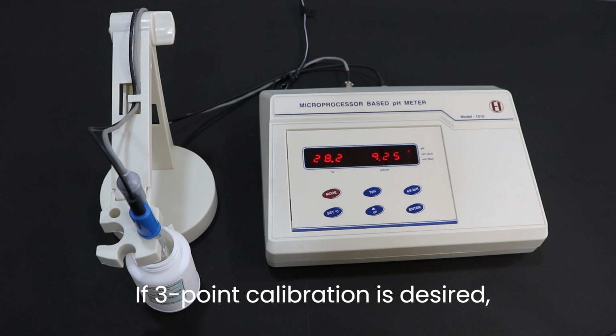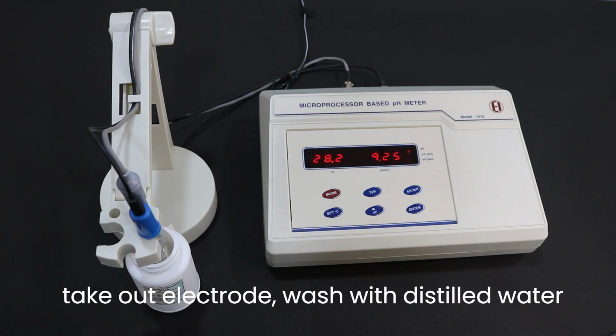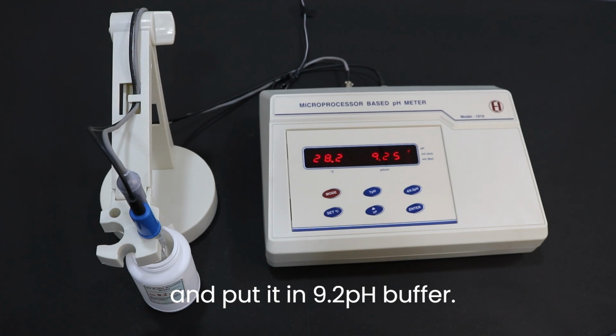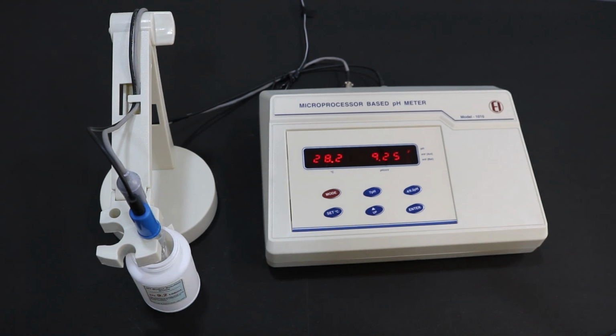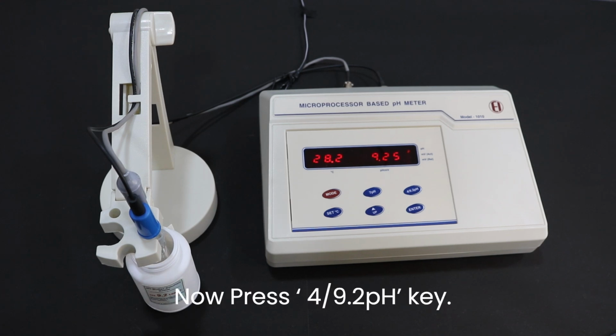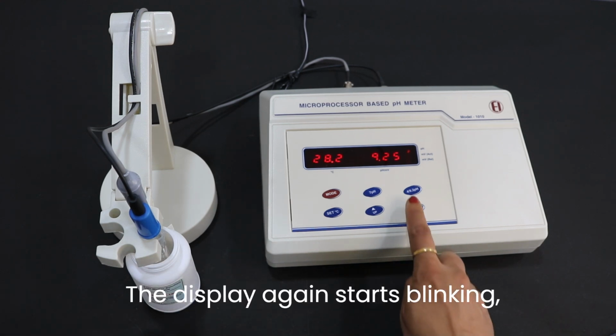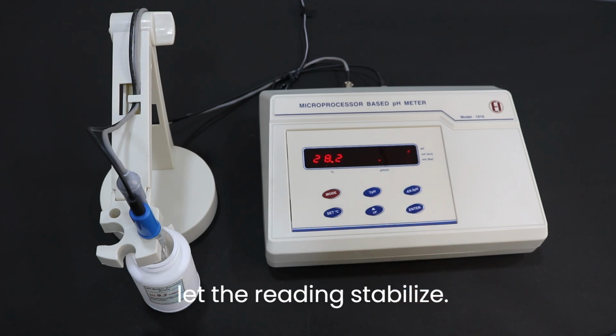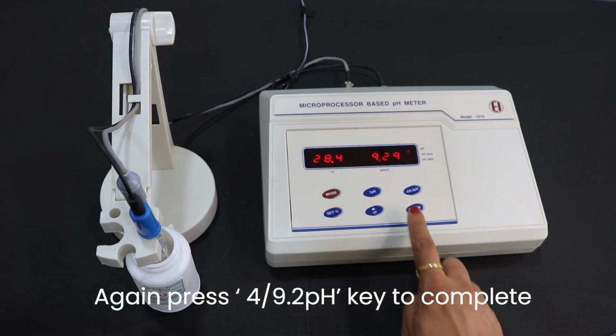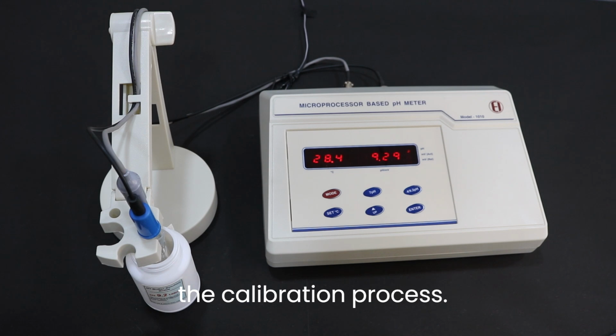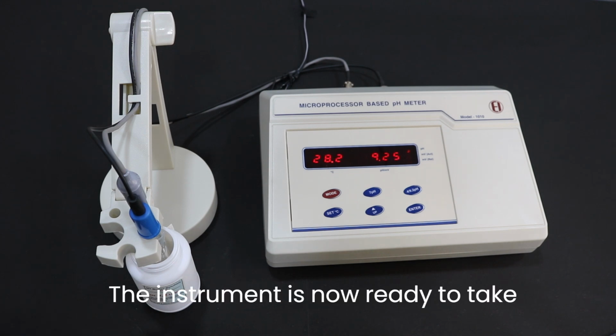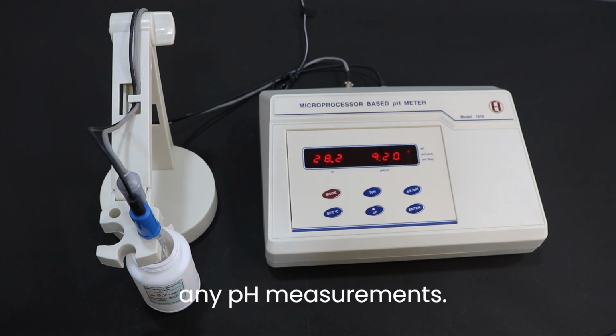If 3-point calibration is desired, take out the electrode, wash with distilled water and put it in 9.2 pH buffer. Now press 4/9.2 pH key. The display again starts blinking. Let the reading stabilize. Again press 4/9.2 pH key to complete the calibration process. The instrument is now ready to take any pH measurements.